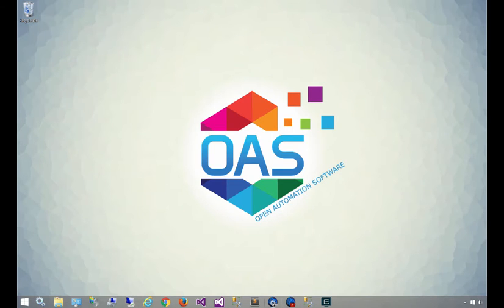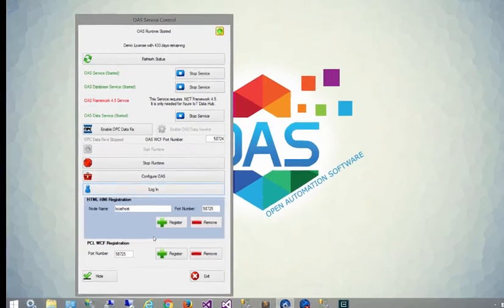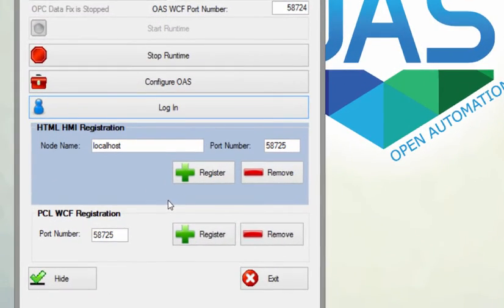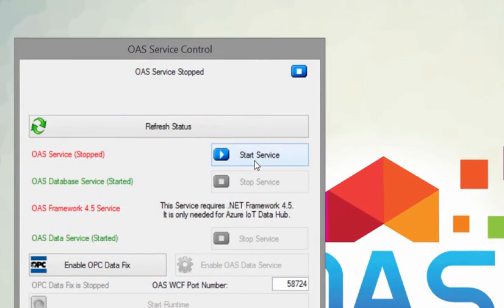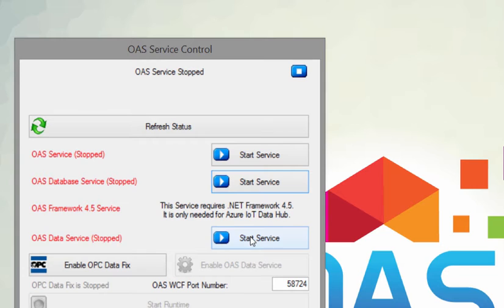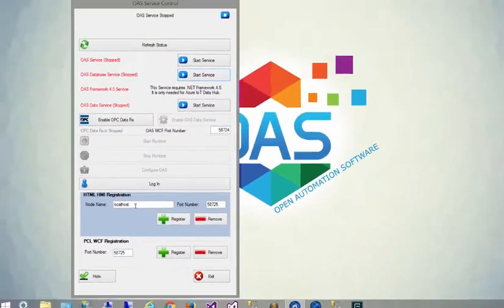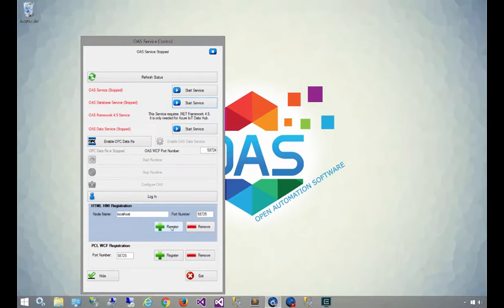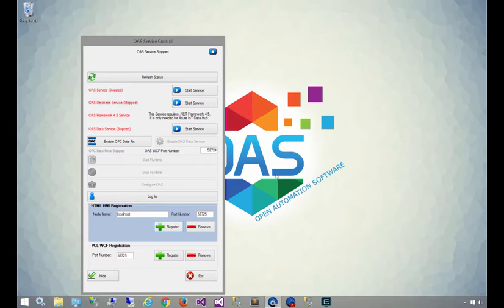Our first step is registering a listener on the server side. This is done by opening up the service control utility, and you'll see the HTML HMI registration. Before you do anything, stop all of the services, and once they're stopped, go down to the HTML HMI registration section and click on register. You can use the defaults for now, but in the future you can change the host name and port number. Once the registration succeeds, you can start all the services back up again.